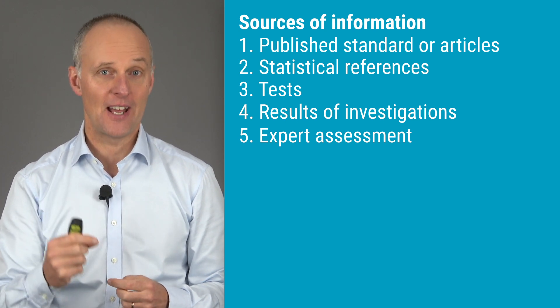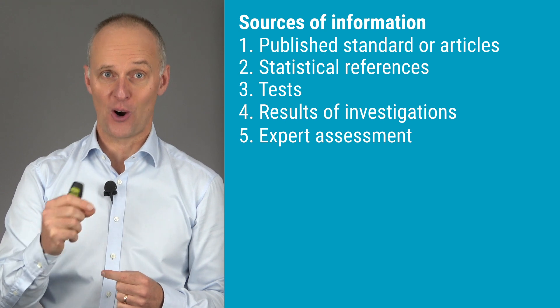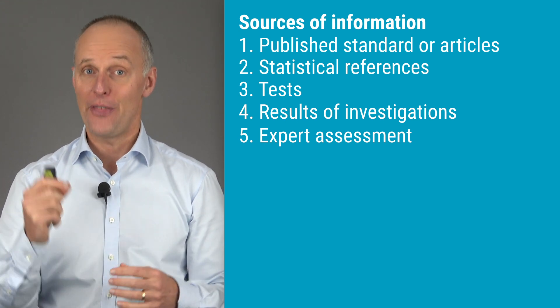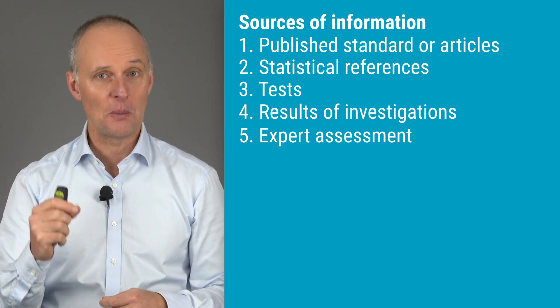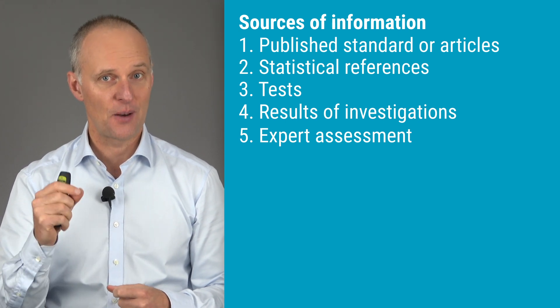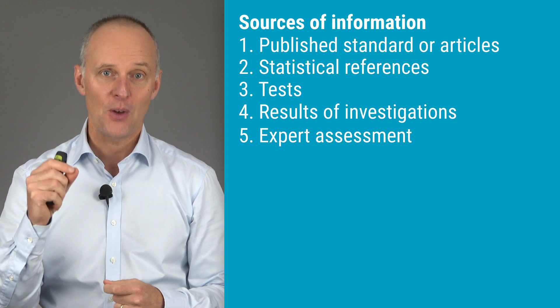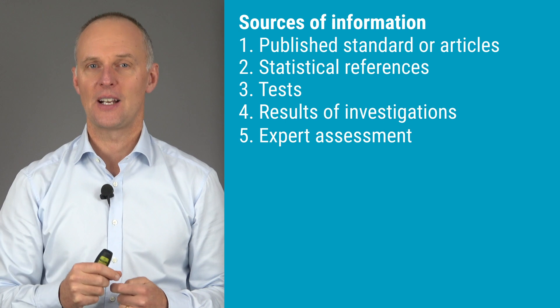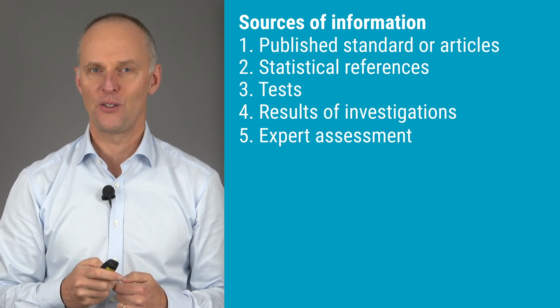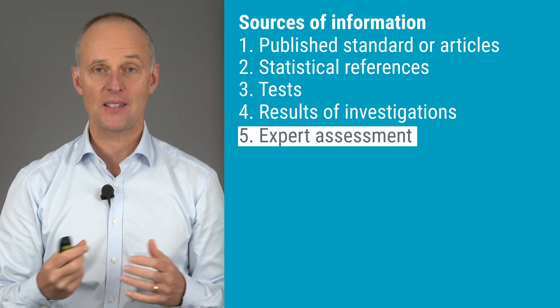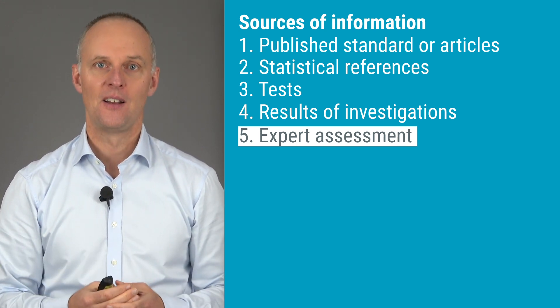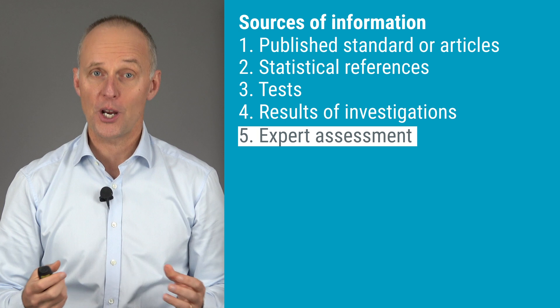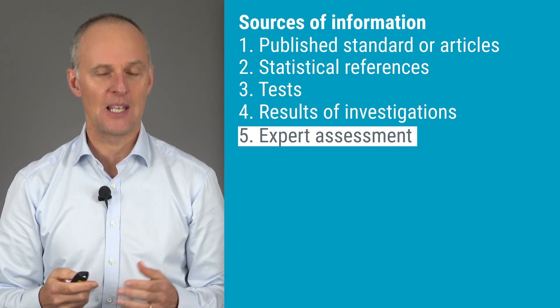Of course it would be great if we could all use published standards, articles, or statistical references for all the risks in our hazard traceability matrix. That is, however, not the case in reality. If you have a brand new product and no one else is manufacturing a similar product, you will find that most of your risk estimates are based on the last option — expert assessment. And this is just a different way of saying that we guessed. Knowing that most estimates are done this way usually comes as a great relief to many people who are worried about these things. If you are making guesses, trust me, you are not alone.